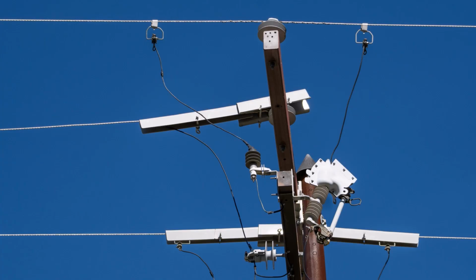Here's a photo of both protection devices, the cutout and the fuse holder, along with the avian protection cover, the cutout's lead wire connected to the main distribution conductor. Over here we see the lightning arrestor. This one is connected to the distribution conductor separately. The cutout and fuse protect personnel and equipment from overcurrent problems that occur on this side of the system, while the lightning arrestor protects from overvoltage issues happening on this side.